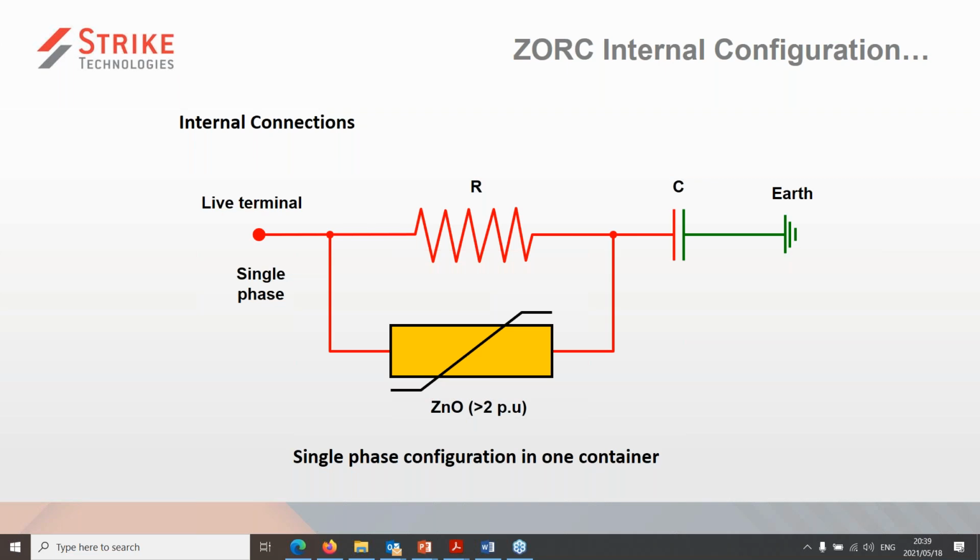With regard to the MOV, these zinc oxide arrestors have a particular knee point voltage that, when activated by the high frequency transient, would trigger and provide a very low resistance path in series with the capacitive element. So therefore you have that suitably low absolute limit that I spoke of earlier, and that suitably low limit is provided for that high frequency steep wavefront transient, and effectively provides that extremely low resistance path, takes that high frequency transient through the capacitor down to earth, solving your problem of having damage done to the windings of your piece of equipment.